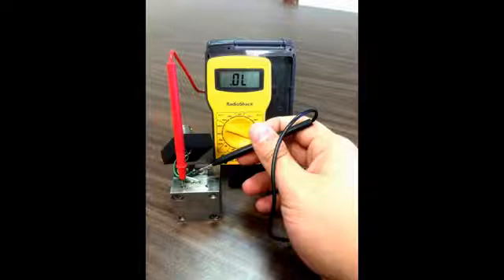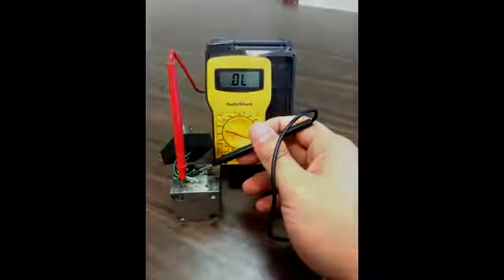If the reading is greater than 100k ohms the sensor will probably work. A reading below 100k ohms means there has been a breakdown in the isolation between the coil wires and the metal case. This often causes drift or noisy pressure readings from the sensor.